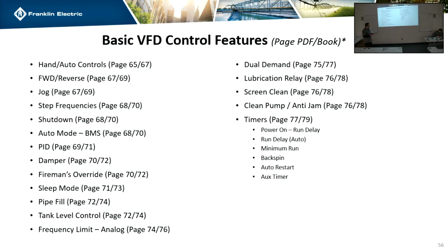All right, Fireman's override is on the same page. Same kind of thing. You've turned Fireman's override on, or you set one of the inputs to Fireman's override. It's going to ask you, when you activate Fireman's override, do you want the drive to automatically run, or do you want it to wait for a run signal? Again, it just depends on the type of fire system you want.